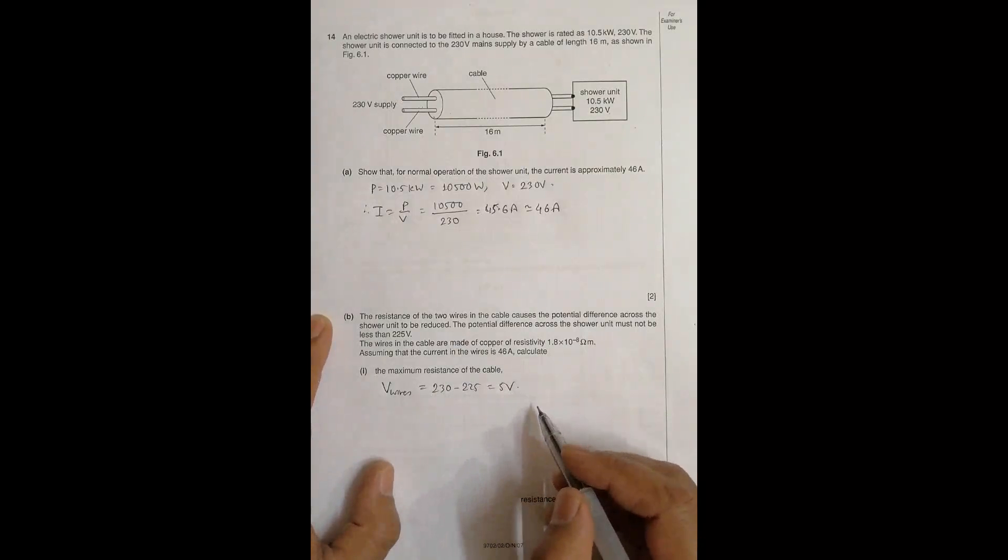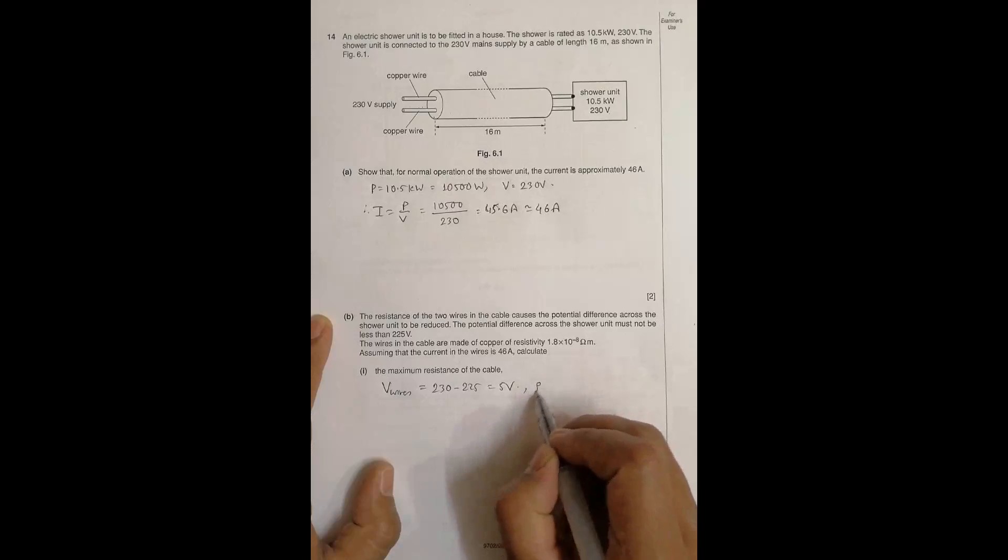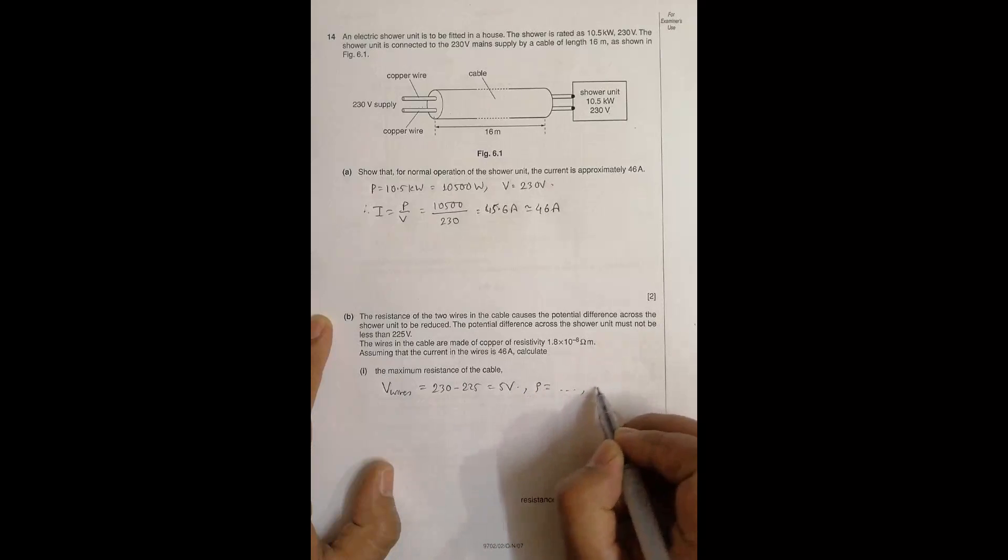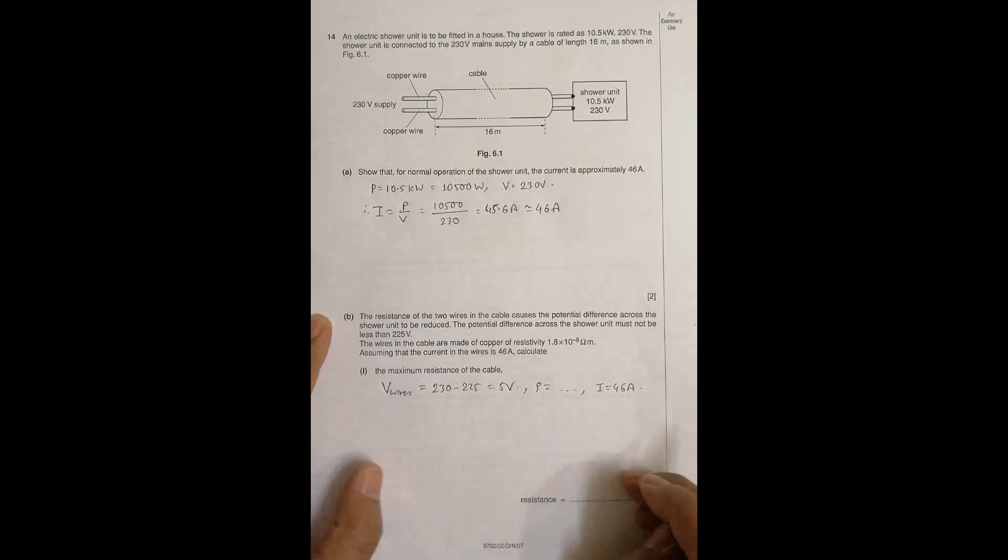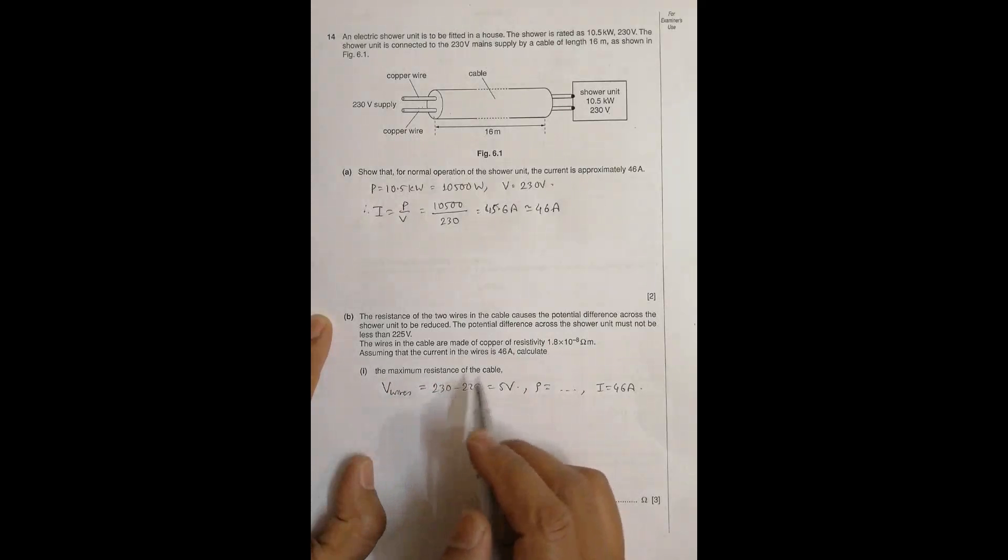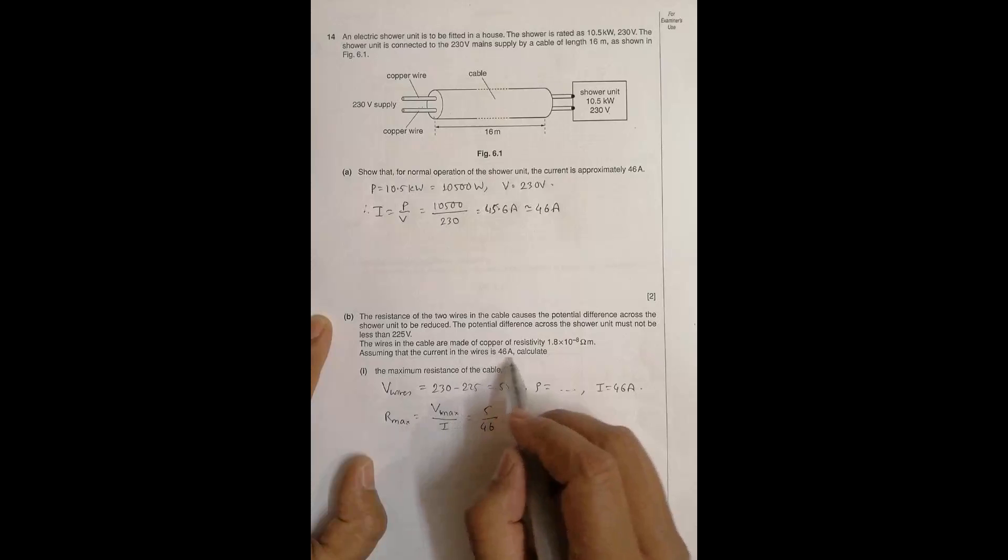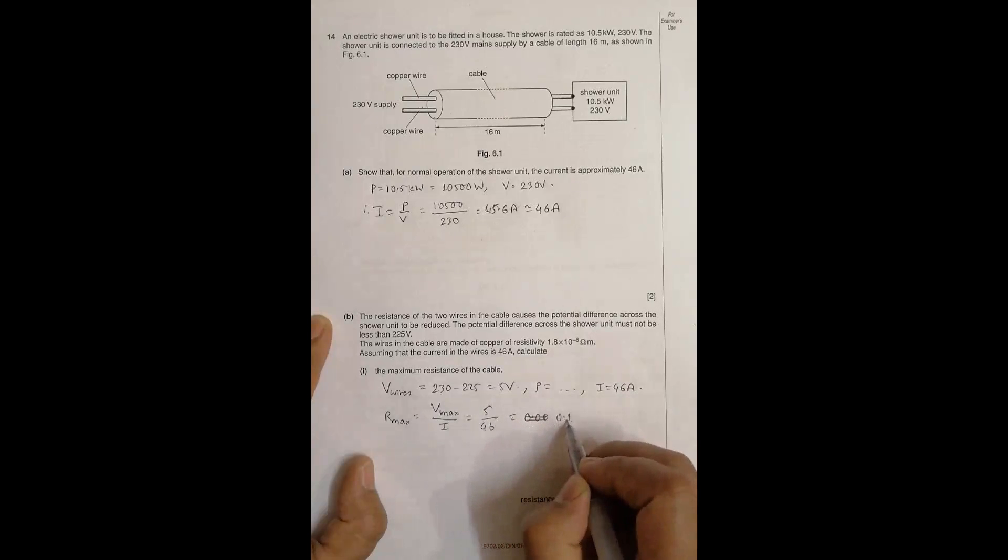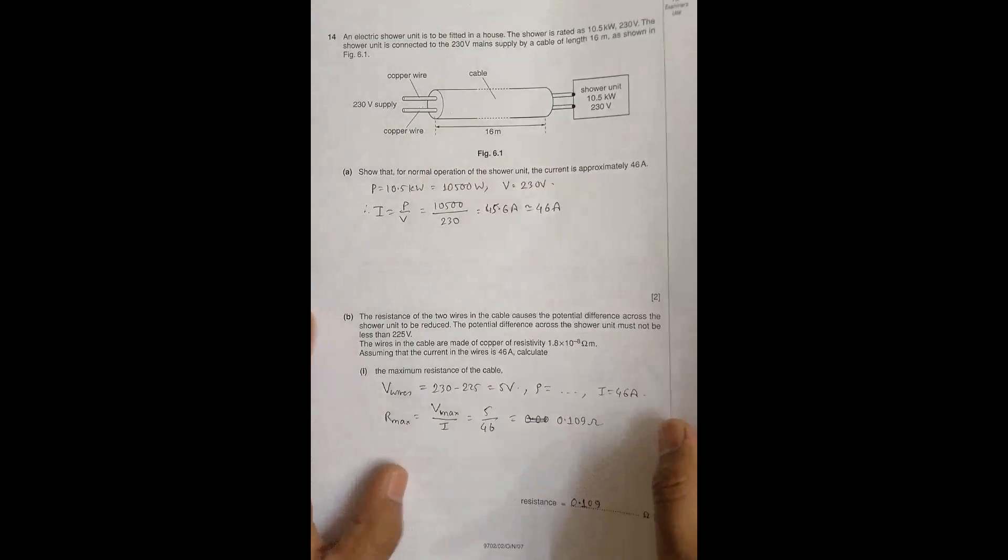We are given the resistivity and current is again I equals 46 ampere. We have to find the maximum allowed resistance of the cable. So R max should be equal to V max in the wires divided by the current, equal to 5 volt divided by 46. This gives 0.109 ohm. So the maximum resistance allowed is 0.109 ohm.